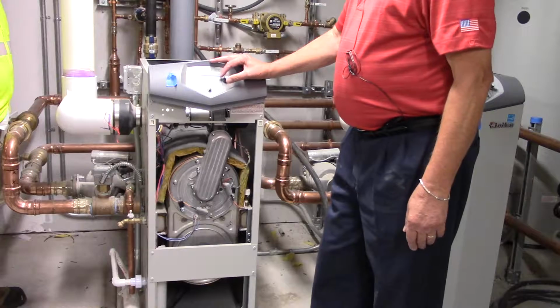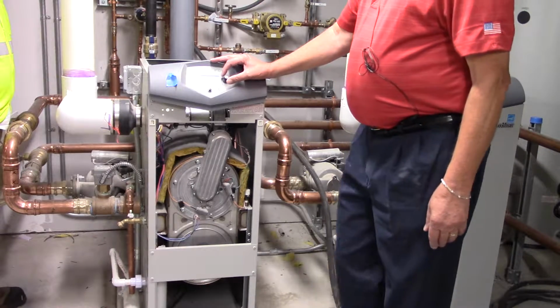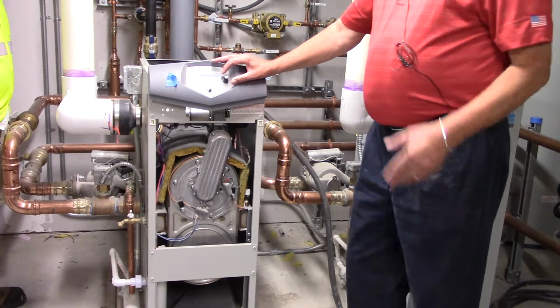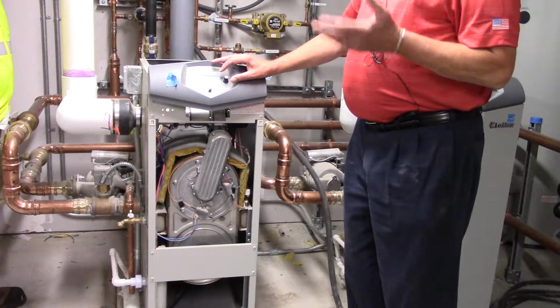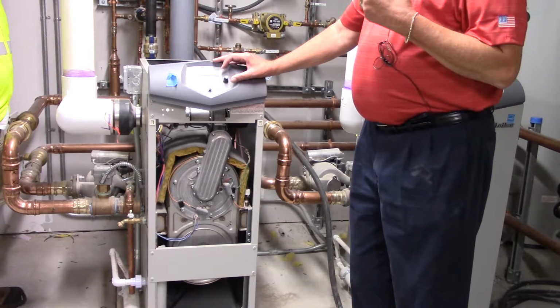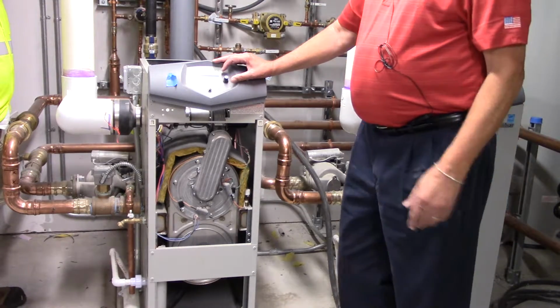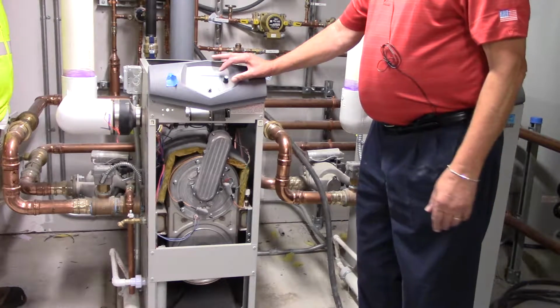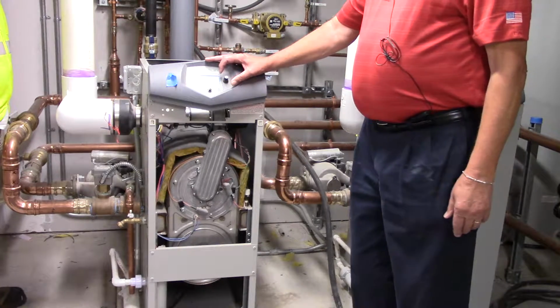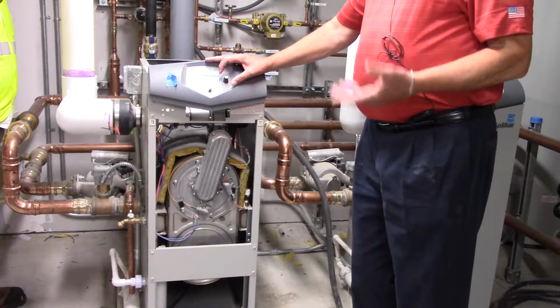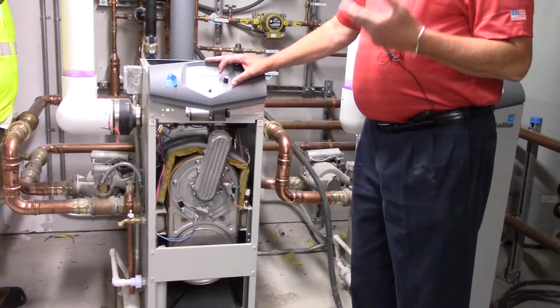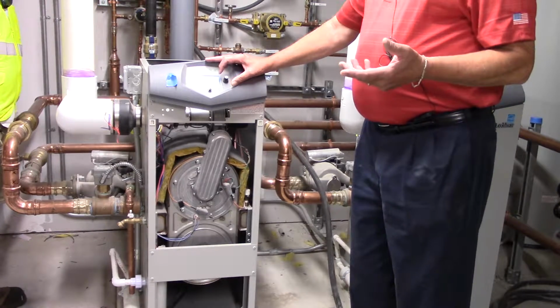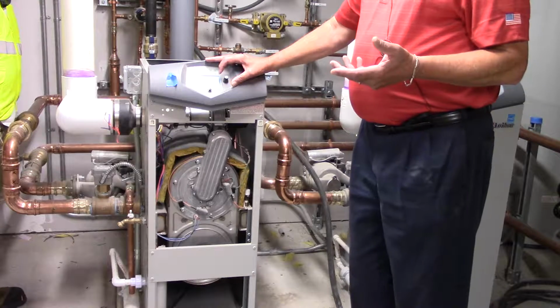So this is going to give you your flame current in microamps, and you should see it at 100%. It's in double digits. It's above 10. That's right on time. So if you see that this microamp reading at full fire is 8 or 9, then you need to be looking for a new flame sensor and a new igniter.